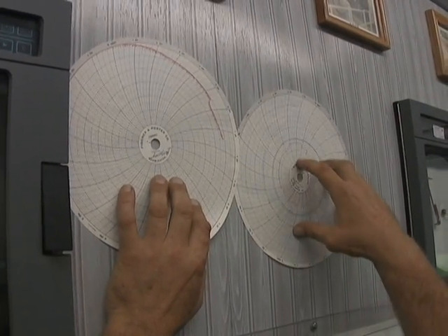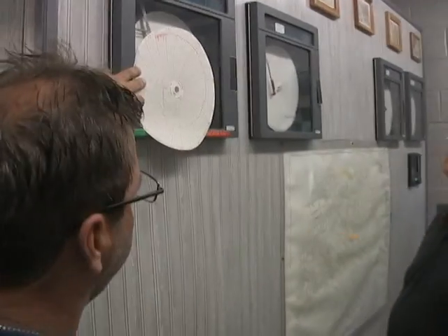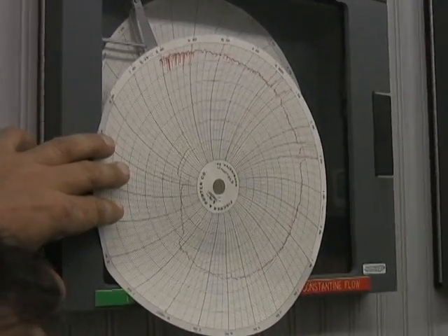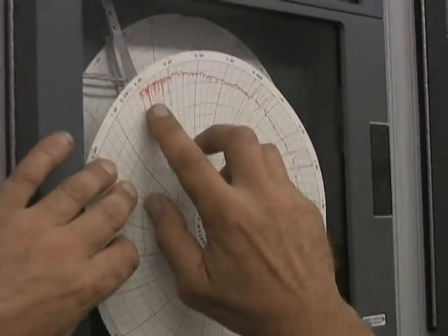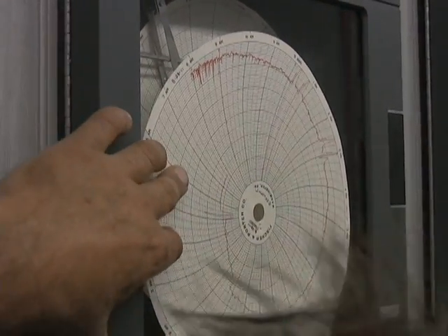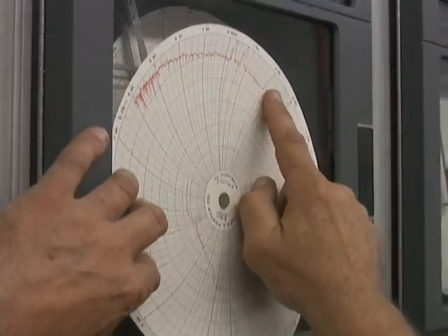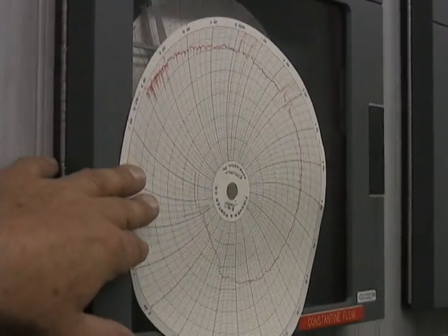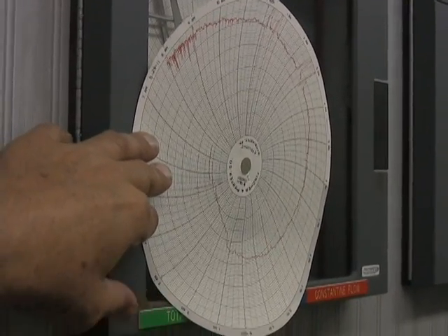And then this is our 3 million, and then really what I would have to show you is our effluent chart. And then what Mike is saying is, you're looking at the chart and I would say probably close to 8 million gallons coming in that day. So here you see, this is the effluent chart, and this is what is actually going to the river. So we have almost 5 million going to the river, 3 million going to Summit, which is a total of 8 million, and we probably got close to 1 million recirculating through the plant, through the filters, and being just processed around.